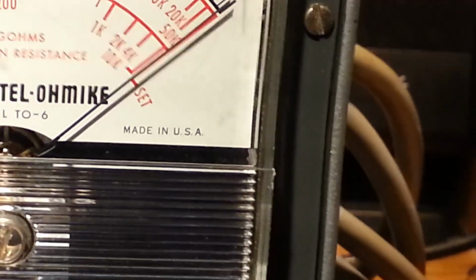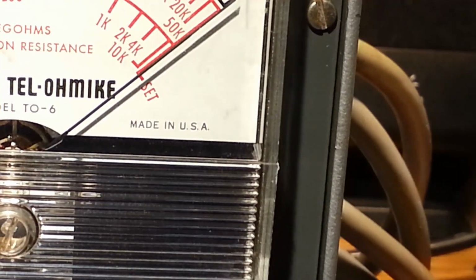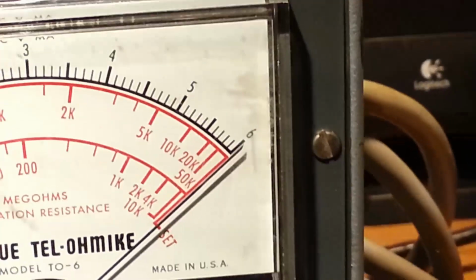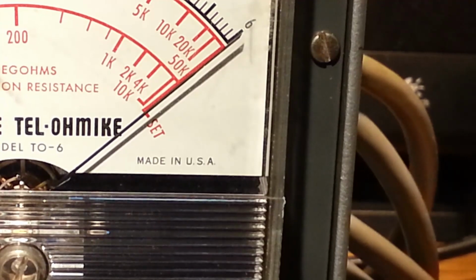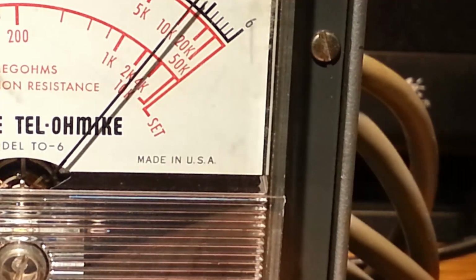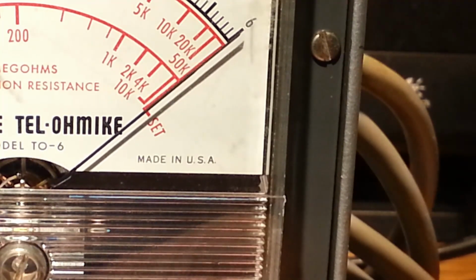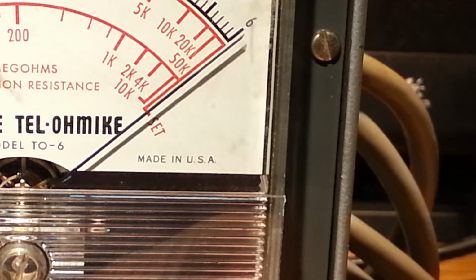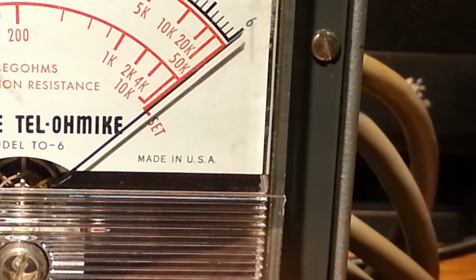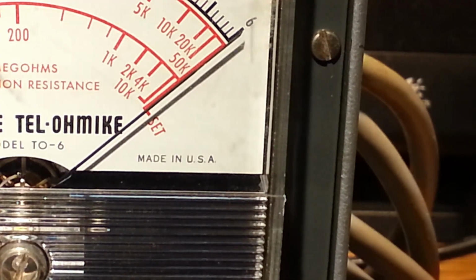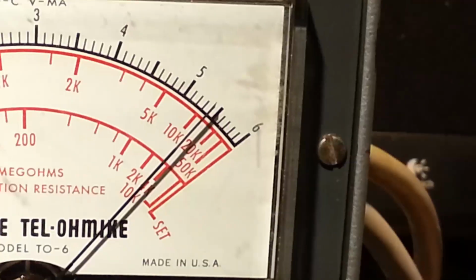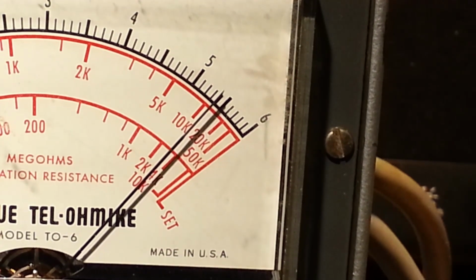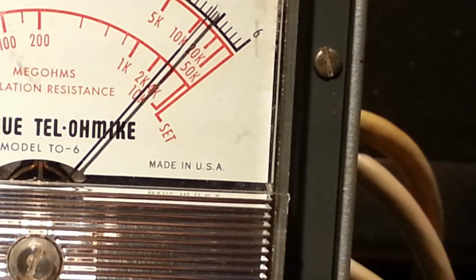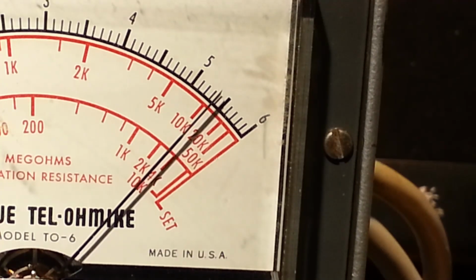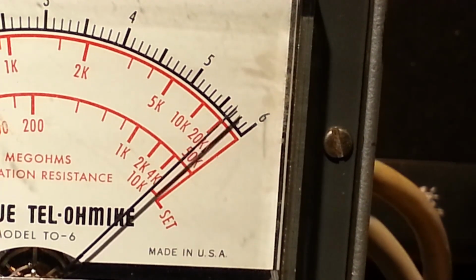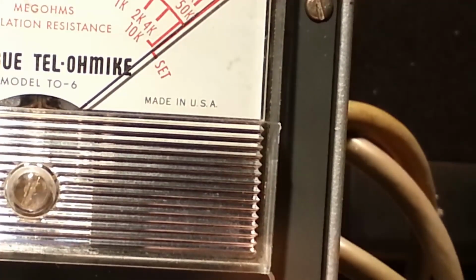So on the 10 kilo-megohm range, that is very accurate. So we're going to change to the 50 kilo-megohm range here. I've got this in discharge. I'm just going to press the 50 kilo-megohm button. I'm going to recalibrate my set point, and going to go from discharge to test, and it's off just a little, but pretty close. It's not an exact quantitative function value, but it's pretty darn close.